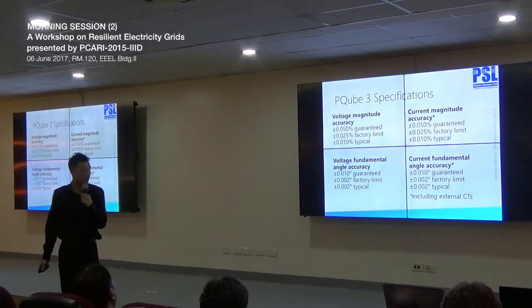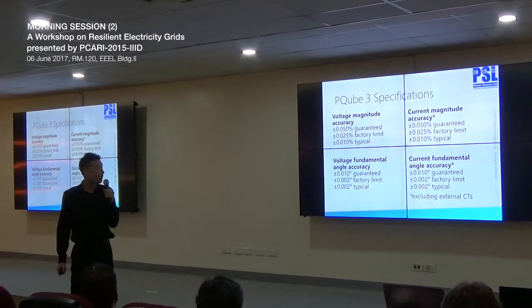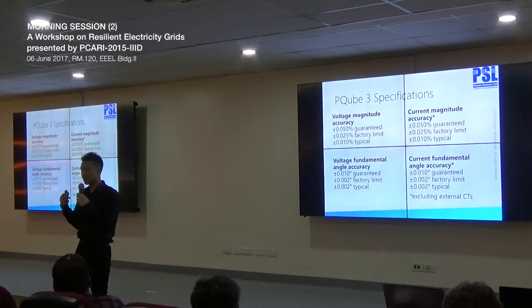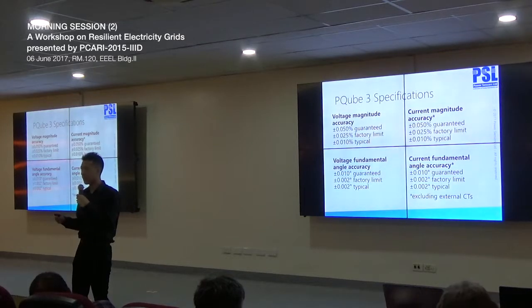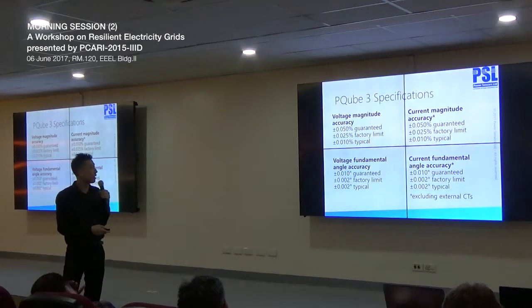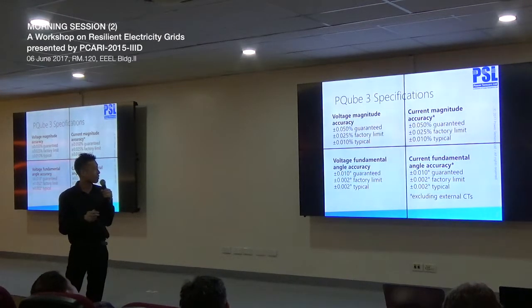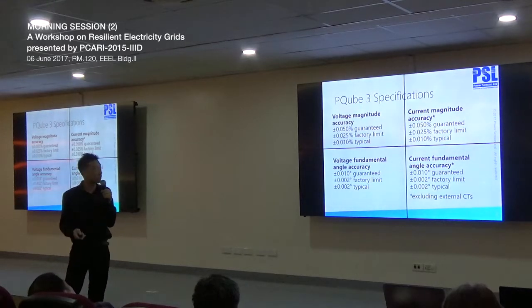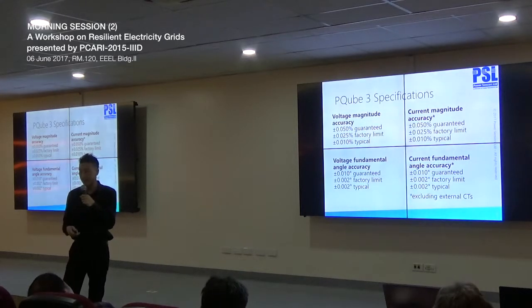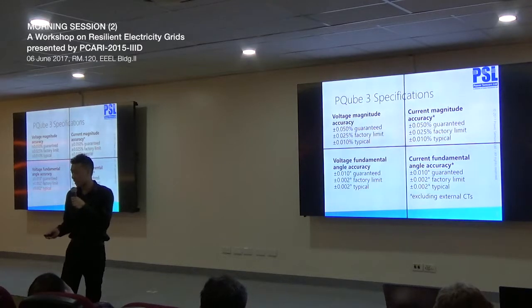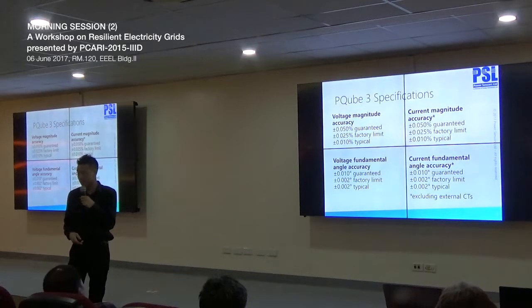Okay, so the PQube 3, we've taken a lot of trouble to make the PQube as accurate and precise as possible, because that's the requirement from all of our customers. Now, if you look over here, you see our specified accuracy is plus minus 0.05%. But in reality, when we calibrate all of our PCubes, our factory limit is half of that. And typically, when we calibrate a PQube, it's actually 0.01% of our reference.